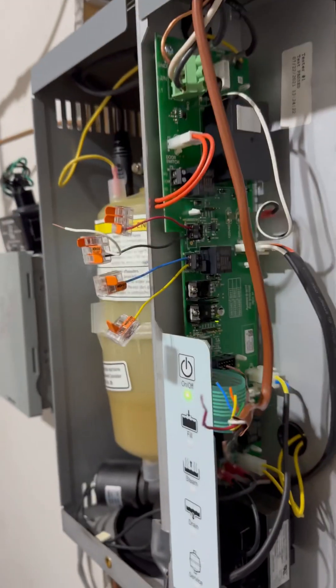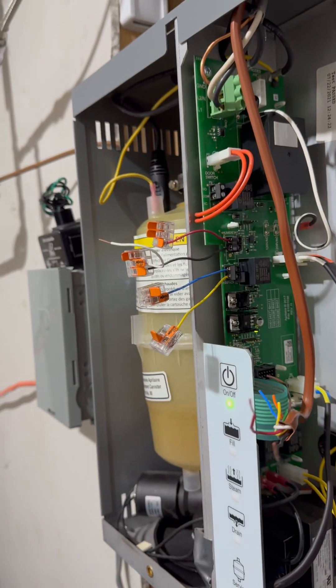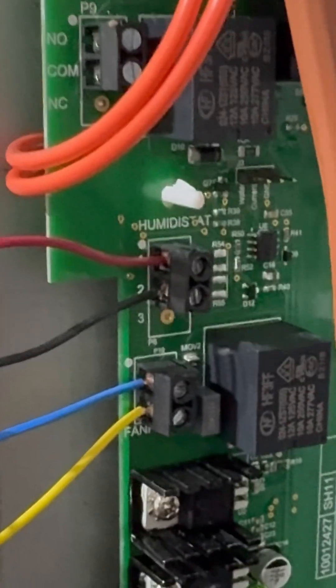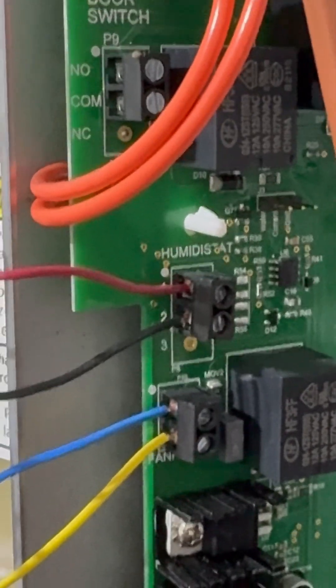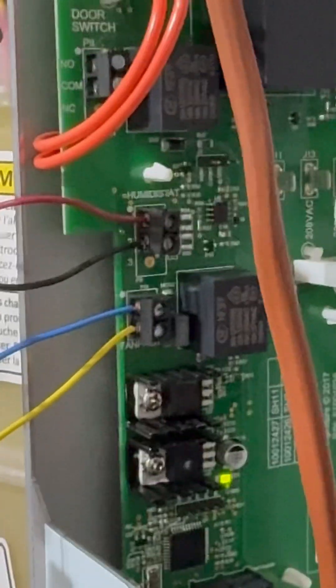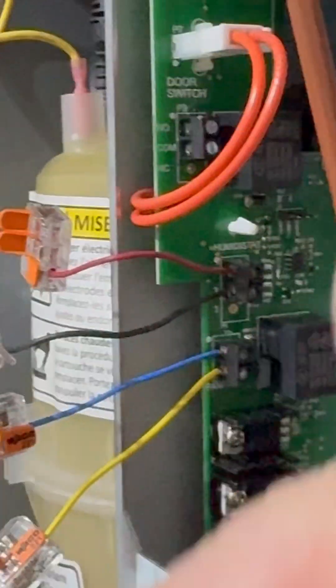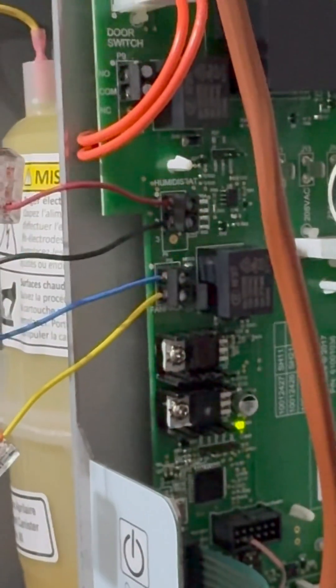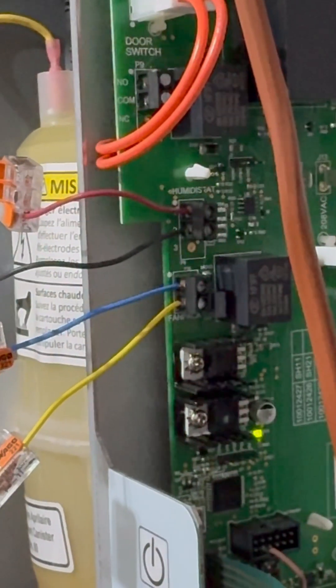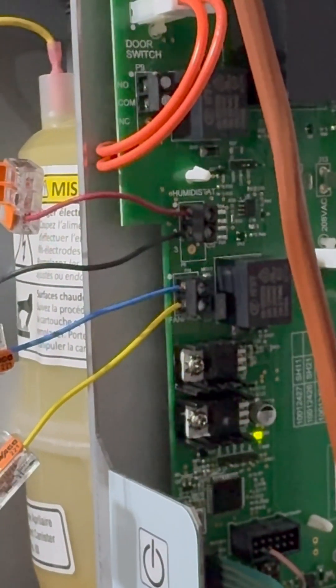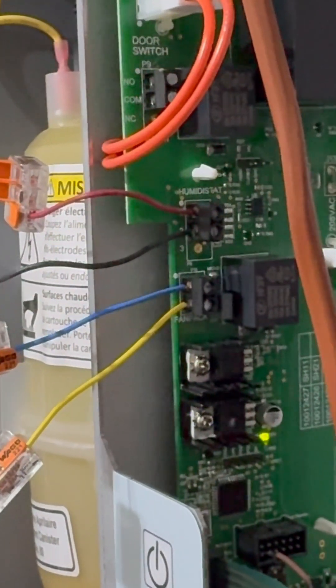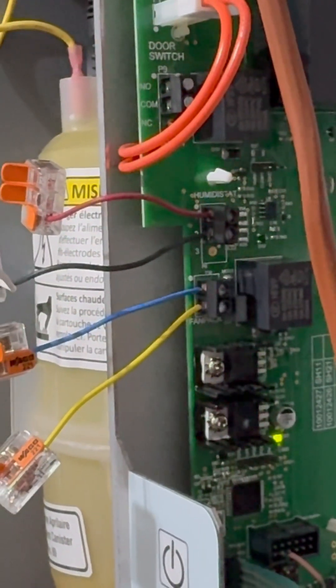All right, I wanted to show how an Aprilaire steam humidifier model 800 works. It uses terminals called humidistat one and two, which receives dry contact - it's a simple on and off switch. It doesn't have any voltage, just requires it to open or close in order to activate.